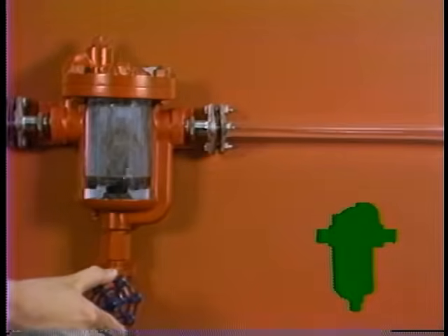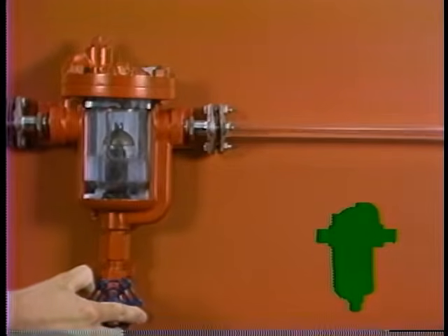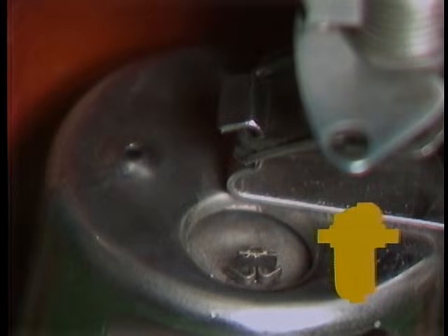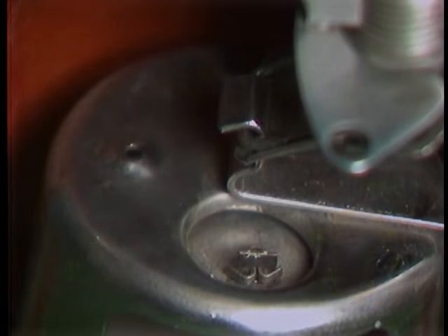The manual metering valve of the DC provides a controlled bleed for startup air loads. The small bucket vent of the IB trap is sized to prevent live steam loss, but may cause temporary air binding during startup. The addition of a thermic vent to an IB passes large startup air loads, but closes to conserve energy when the system reaches operating temperature.